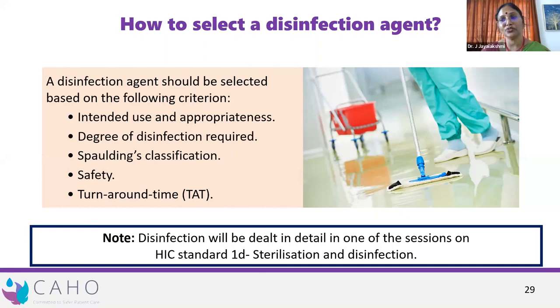Like I mentioned, if you use sodium hypochlorite on a stainless steel surface, it will corrode. A lot of people during COVID used sodium hypochlorite for decontamination. As per recommendations, you can use sodium hypochlorite or alcohol. That was a common, simple recommendation for all facilities to follow, and a good one. However, it also clearly mentioned not to use it on steel. But a lot of facilities now have rusted instruments and trolleys because of overuse of sodium hypochlorite.